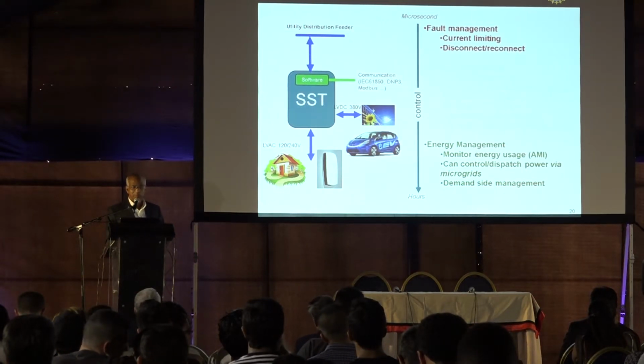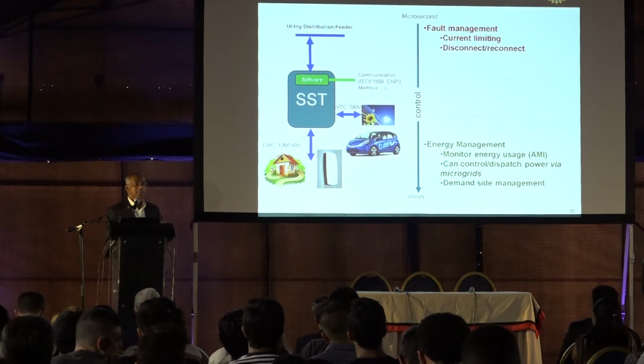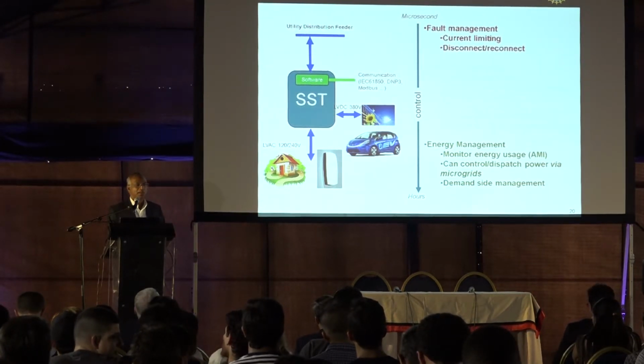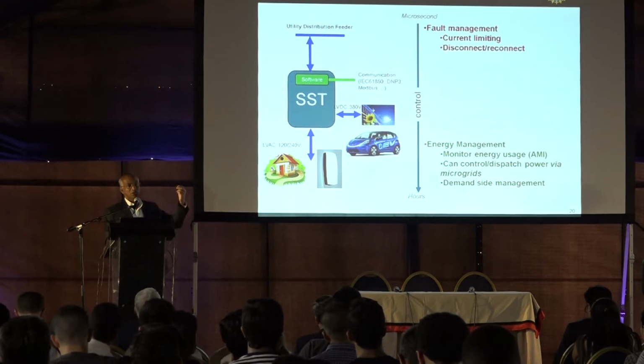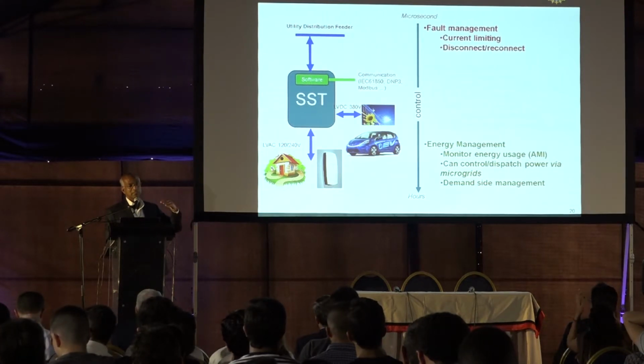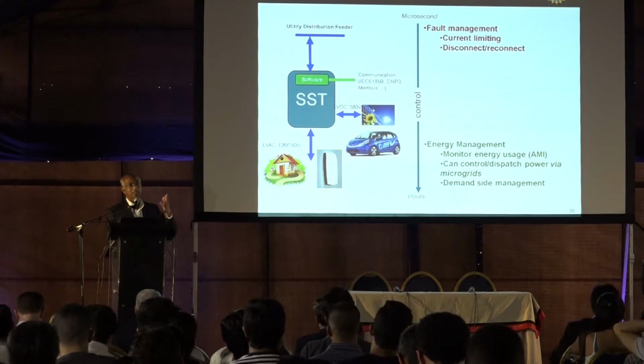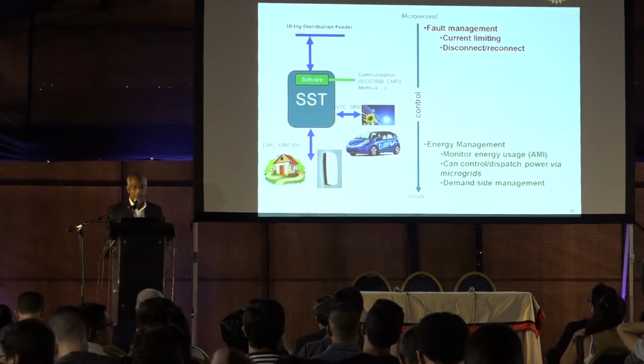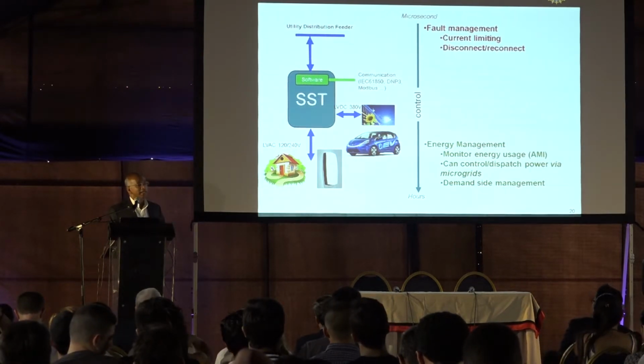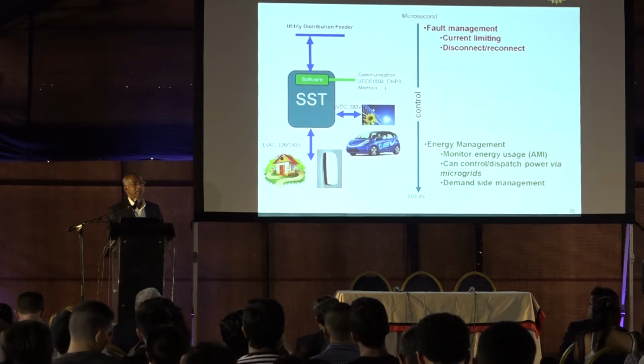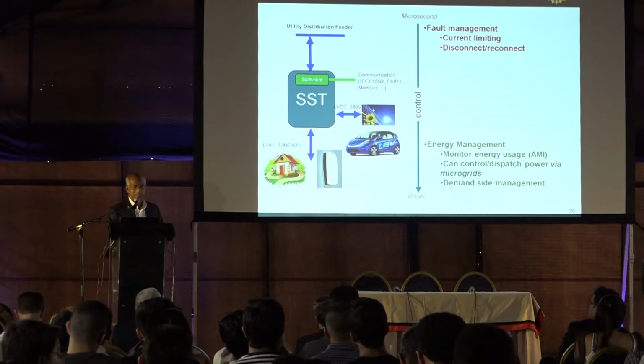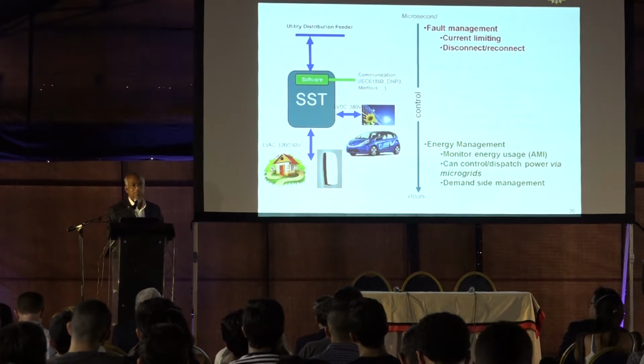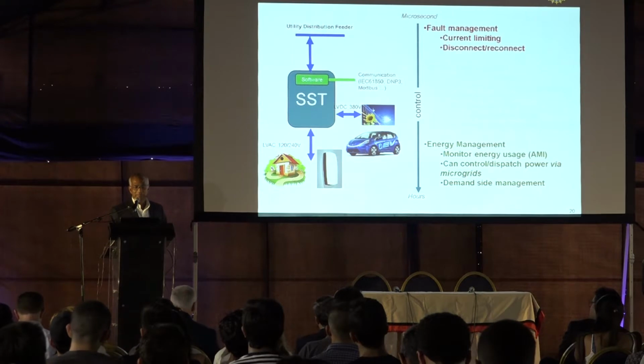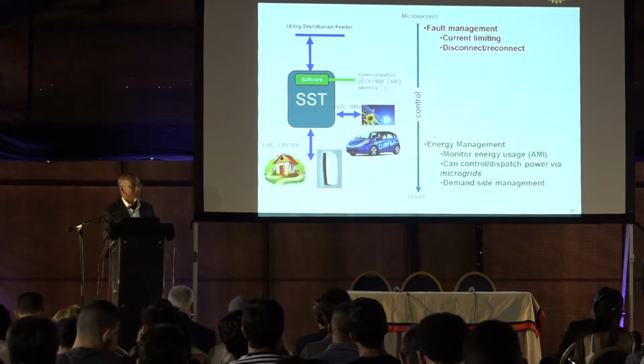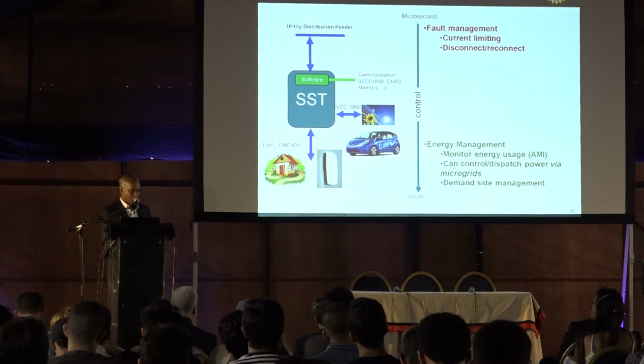It can provide us with power management, for example, introducing reactive power or power factor, and help with demand side management. In case there is a fault, it offers low voltage ride-through, so the voltage dips, but the transformer controller can handle that, and it should be able to ride through that fault. And then at a higher level, it can do energy management, like connecting to advanced metering infrastructure, demand side management or dispatch controls. All of these can be very intelligently managed by this solid-state transformer.